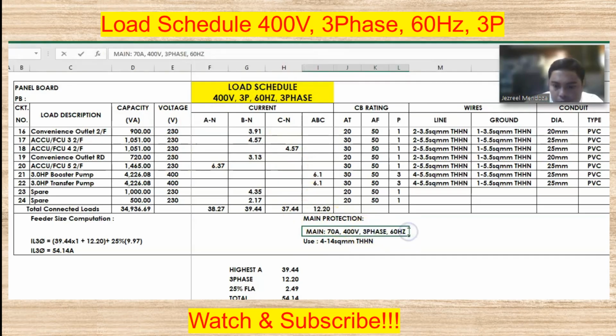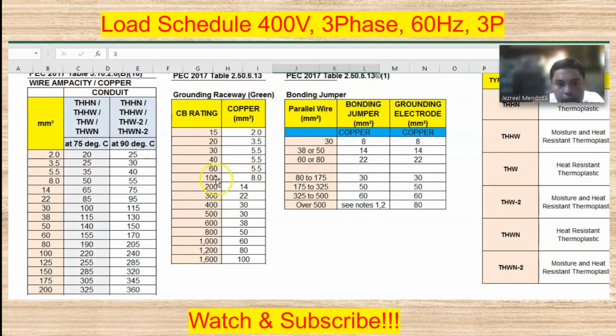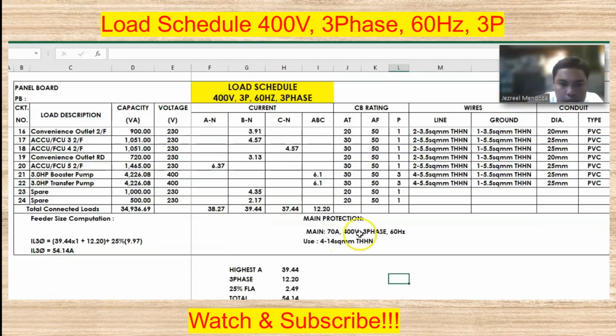And then for the ground wire, if you look to the PEC table, for 70 amperes, it falls between 60, which is 5.5, and next is 100, that is 8.0. So we can use 8.0 for the ground.